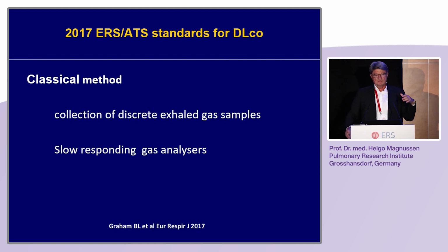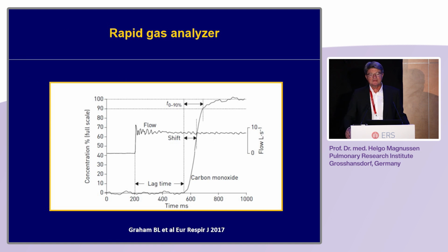And therefore, you have a better estimate of alveolar volume and also a better estimate of the CO uptake. And this is also a great advantage. Now, these rapid gas analyzers, as the name says, have a response time to a change of gas in milliseconds. And many years ago, this was not milliseconds, but seconds.